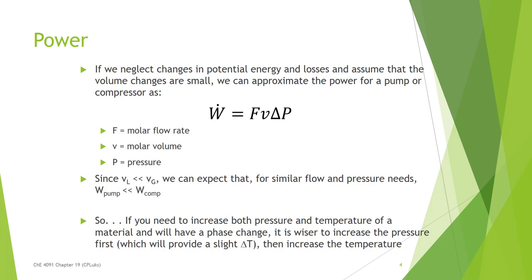If we have a similar flow rate and a similar change in pressure, the molar volume will make a large difference. If I have a fluid and I'm going to work with it sometimes as a liquid and sometimes as a gas, I'm always going to do much better to pump a liquid than to compress that gas because the volume is smaller for the liquid. So whenever I've got a stream where I need to change both pressure and temperature with a phase change, try to do the pressure change first and then change the temperature to the gas phase. If you're going from gas to liquid, wait until it's in the cooler liquid phase and then change the pressure. You'll save a lot of money in your operations cost.